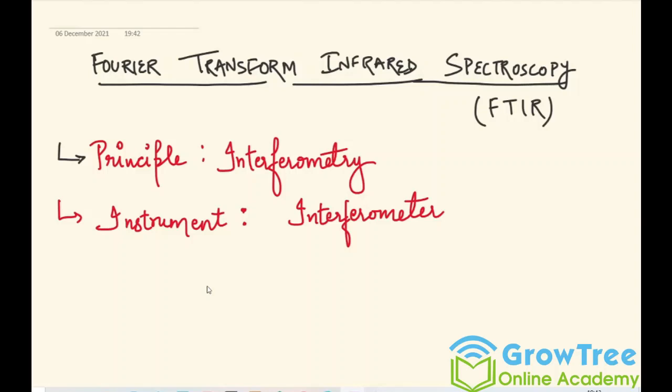In today's video, we are going to discuss FTIR. FTIR stands for Fourier Transform Infrared Spectroscopy. The principle and instrumentation of FTIR is quite different from dispersive IR, and in most of the laboratories, FTIR is used. The principle on which it is based is interferometry, and the instrument is known as an interferometer.